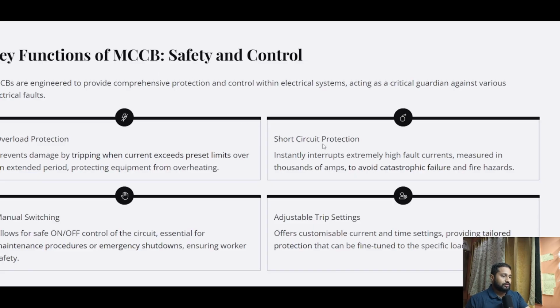Then next function is short circuit protection. MCCBs instantly interrupt extremely high fault currents measured in thousands of amperes to avoid catastrophic failure and fire hazards. Then it also offers manual switching, which allows for safe on and off control of the circuit, essential for maintenance procedures or emergency shutdowns, ensuring worker safety. Then it has adjustable trip setting. MCCB offers customizable current and time settings, providing tailored protection that can be fine-tuned to the specific load characteristics. So we can set the time settings and current setting according to our specific load characteristics.